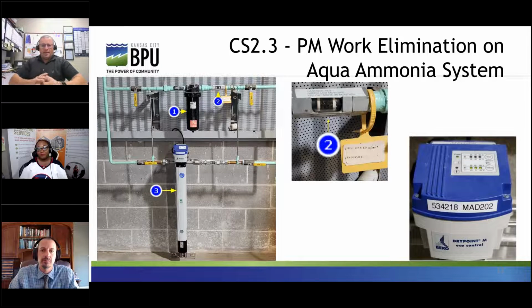This is the last of the ammonia-related slides, but it was worth mentioning because it cut out a bunch of PM work. And unfortunately for the slide, I couldn't locate a previous state photo to use, so we'll have to use the photos I've got in image. Components listed as 1, 2, and 3 are used to ensure dry air is delivered to a 20-pound air blanket on top of the liquid ammonia in our 2 bulk storage tanks to prevent it from boiling.